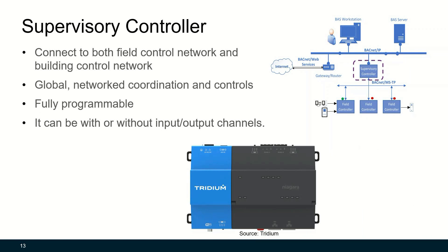The supervisory controller connects both the field control network and building control network. It provides global network coordination and control, and is fully programmable. It can be with or without input or output channels. Data typically comes from the field controllers, passes through the supervisory controller, and is then sent to the workstation or BAS server. Field controllers typically don't communicate peer-to-peer; rather, they communicate through the supervisory controller.